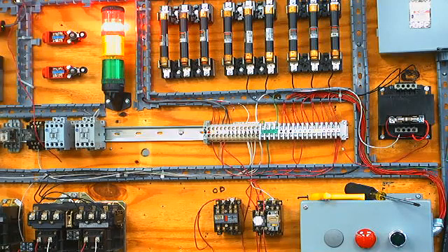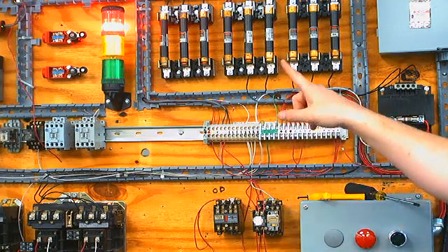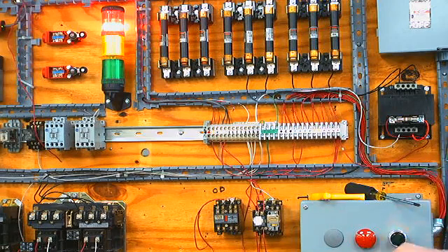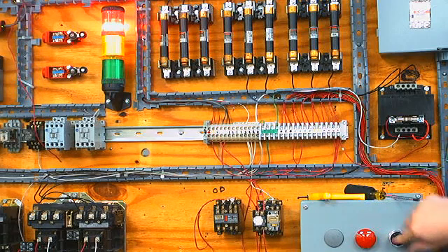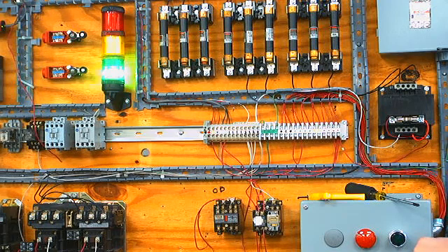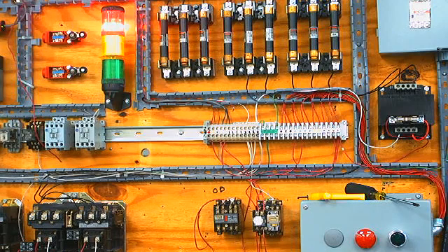It's an off delay timer. So when I push the button, it's going to change state. The green light will turn on, the red light will turn off. When I let go of the button, then a certain amount of seconds later, it will change state because it's an off delay timer. All right. So I'm holding the button down. It changed state, right? I don't know how many seconds this timer is set for. It's probably more than 3, but I'll just de-energize the coil and then you'll see that however many seconds later, 1, 2, oh, that's pretty close to 3.